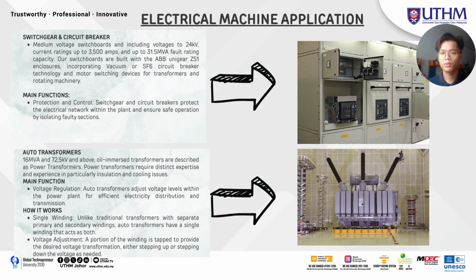The third component is the switchgear and circuit breaker, a medium voltage switchboard including voltage up to 24 kV, current rating up to 3500 amps and up to 31.5 MVA fault rating capacity. Our switchboards are built with the ABB Unigear ZS1 enclosures, incorporating vacuum or SF6 circuit breaker technology and motor switching devices for the transformers and rotating machinery. The main function is to protect and control. Switchgear and circuit breakers protect the electrical network within the plant and ensure safe operation by isolating faulty sections.